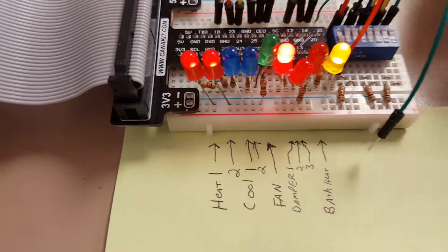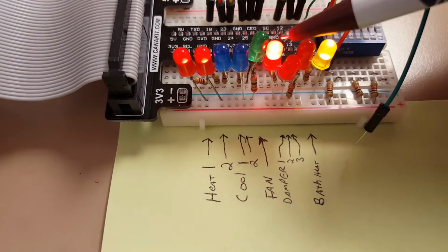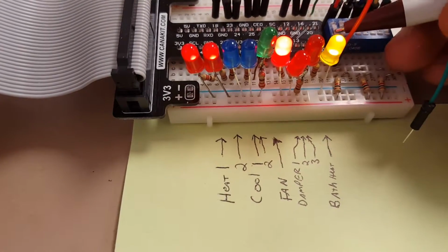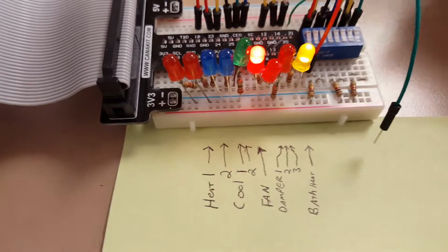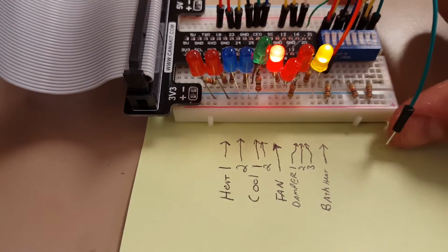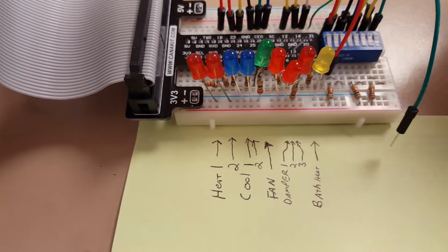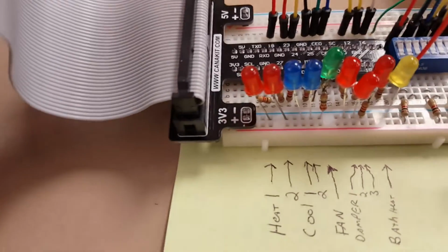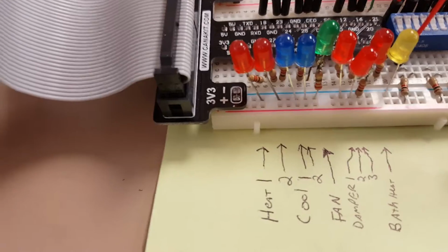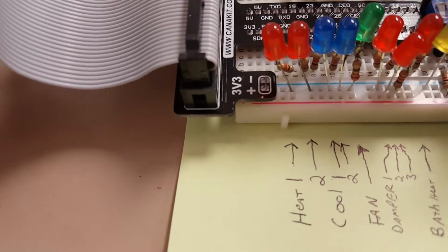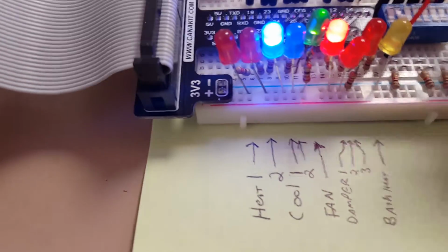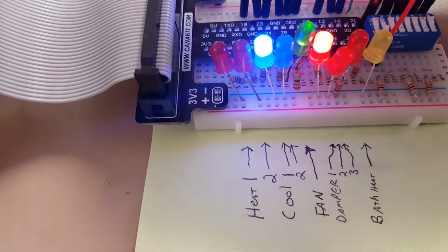The other thing you'll see is a delay in the zone dampers. The last one will stay open for a short time after the heating is satisfied, and that's just to make sure the heat exchanger can cool off before the damper closes. Cooling works similarly. There we go. That damper's open. It also calls for the fan to come on.